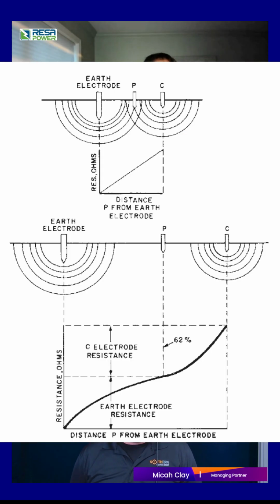And when you're talking about a really large ground grid, right? I've been out at some of these really large manufacturing plants, when they're building and they're literally just digging Earth. They'll go out there and start doing all their ground rods. You're talking about 2,000 feet in one direction by 3,000 feet in another direction, all interconnected ground grid the whole way through. And you're like, well, how do I test this thing as a grid? Well, these documents, IEEE, they're going to say 5 to 7, maybe even 10 times the diagonal length of the grid, right? Because you've got to have this giant sphere. I can't just test a little bit of Earth right next to it. You've got to go 5 to 10 times out, so that way you can scale your meter properly. That's essentially what you're doing, right?